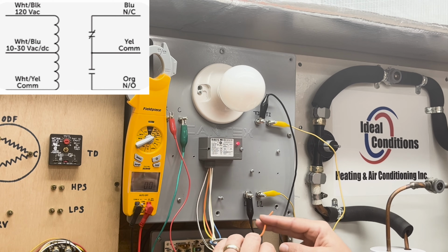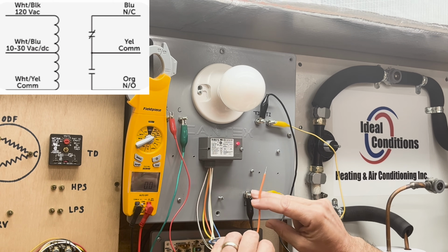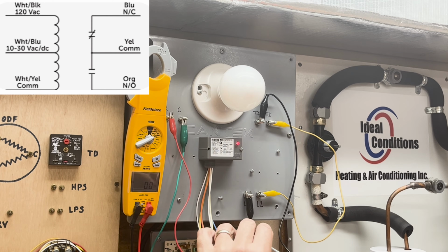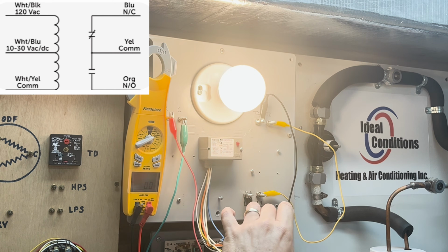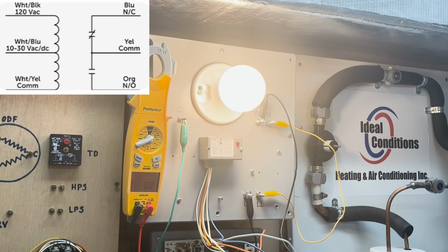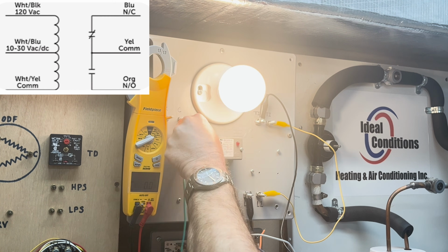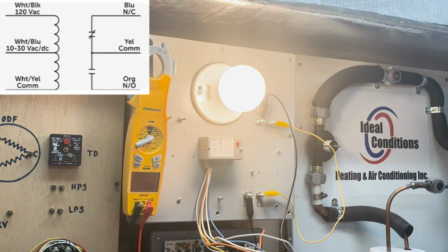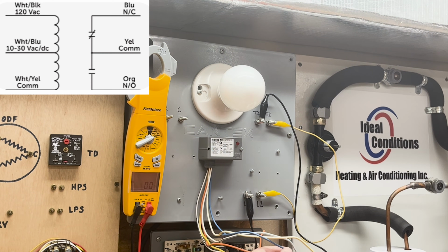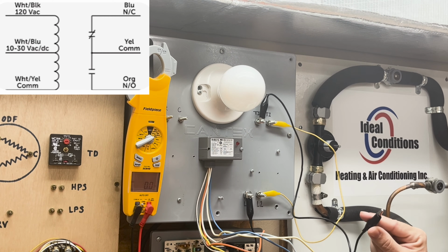I have one spare wire because I'm not using that, and that's going to be my orange. My orange would be my normally open. Okay, I'm going to go ahead and remove coil voltage. As you notice, the red light went off. And I'm going to go ahead and remove my common, since all these wires are just floating here, so nothing touches anything that I don't want it to touch. Let's see here. We want orange to go to T1.